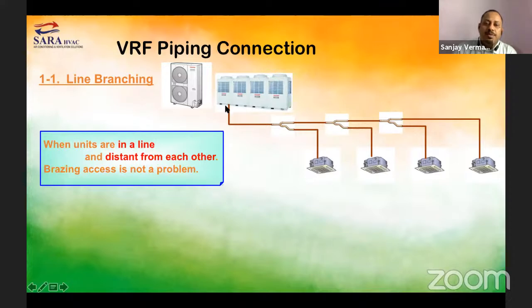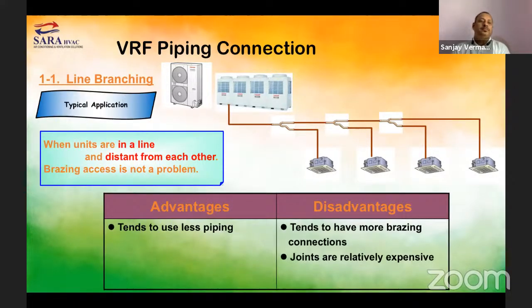The copper pipe comes from the outdoor machine, and in this place you can see there is one white type of copper pipe joint. This joint is called a refnet joint. From here, either the suction line or the liquid line, both can be segregated, putting one as header and the other as branches for their various indoor units. And this will be installed. The copper pipe sizes vary. The starting copper pipe size at the outdoor unit will be based on the capacity and software calculations.